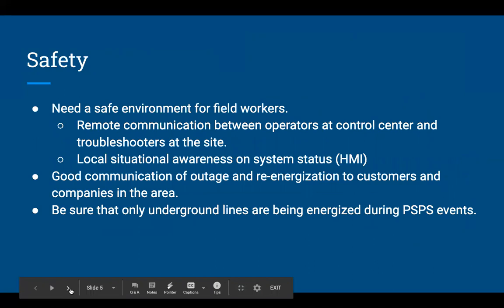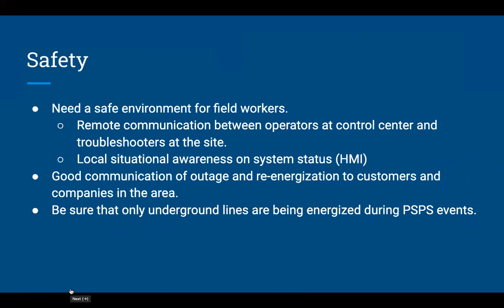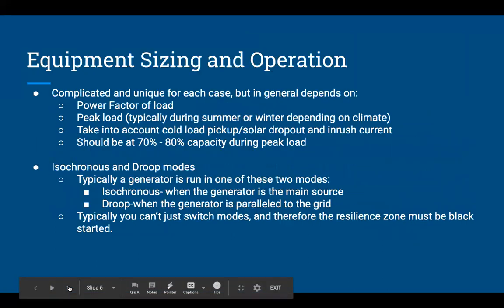A safe environment for field workers is very important. We want to make sure we have remote communication between operators and the troubleshooters at the site. We also want to have local situational awareness for the field workers. Also, good communication of any outages or re-energization to customers and companies. And we also want to make sure that only underground lines are being energized during a PSPS event.